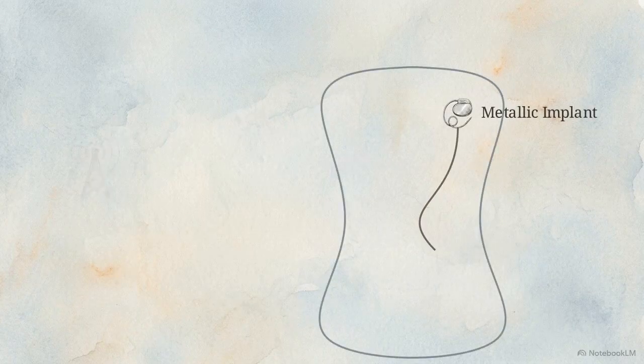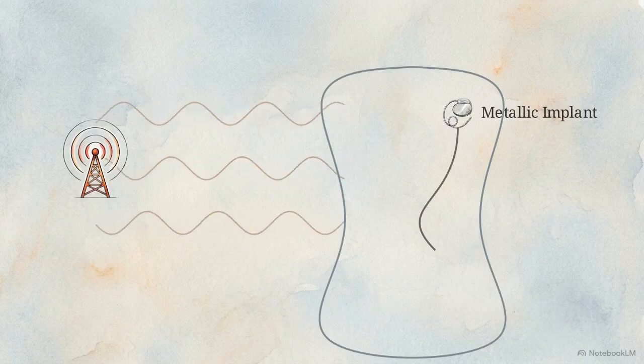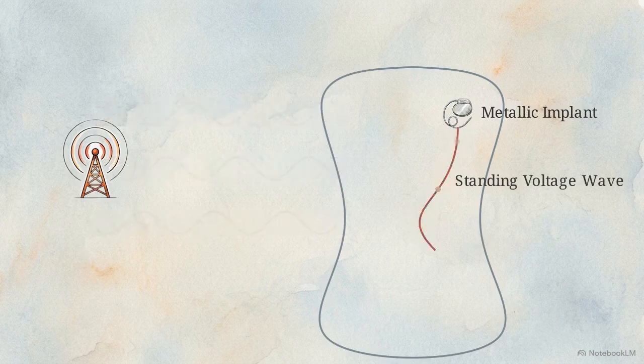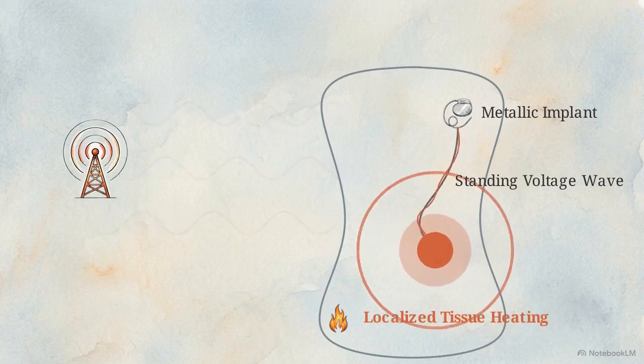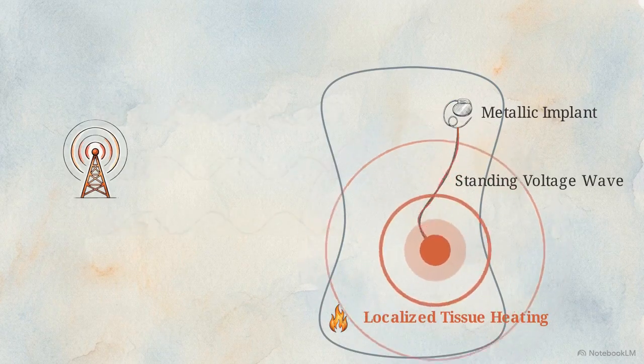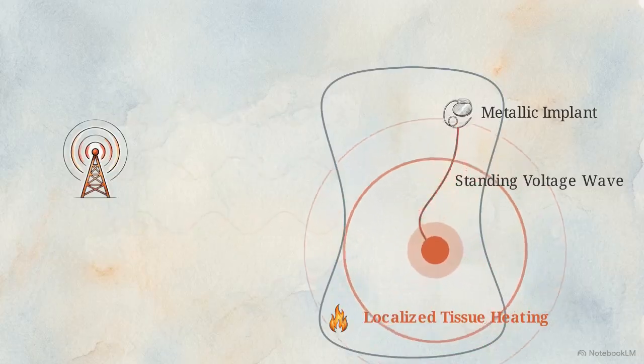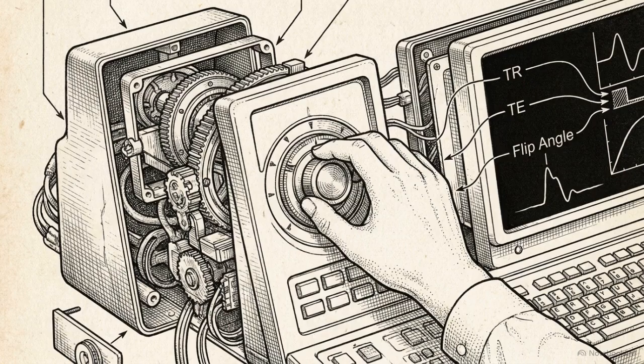RF fields interact with metallic implants through the resonant antenna effect. Oscillating pulses establish a standing voltage wave along a conductive wire, like a pacemaker lead. This energy concentrates at the tip, causing rapid heating and potential burns to surrounding tissue. Unlike the static field, RF hazards are thermal. They convert biological fluids and artificial leads into internal heating elements. Operators must actively manage SAR by adjusting the parameters of the pulse sequence to keep energy deposition within safe limits.